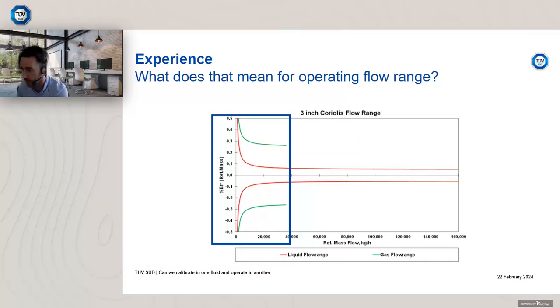And if you are familiar with Coriolis meters, you'll be aware that at the lower end, and this is true for all meters, but for Coriolis meters you get zero effects. For other meters you start to get potentially velocity effects where it drops off, like a turbine meter, for example. But for the zero effects with Coriolis meters, they start to dominate. They start to have a larger relative effect. So it's an absolute number, the zero, but it has a larger relative effect on your performance.